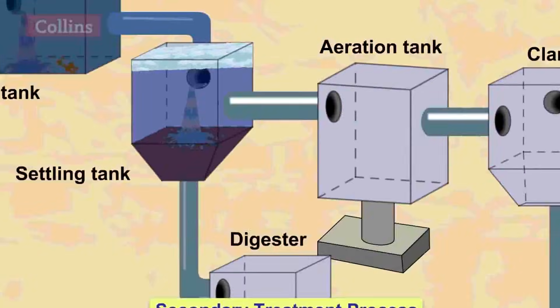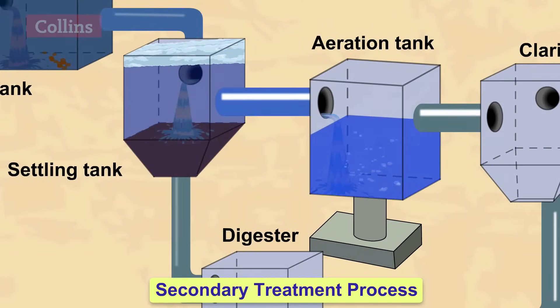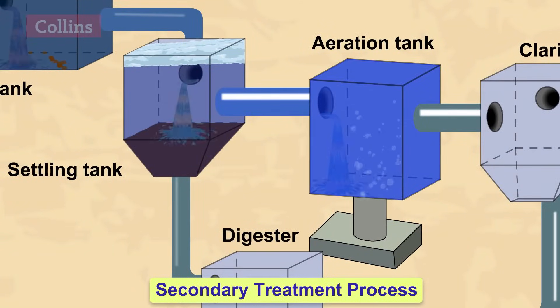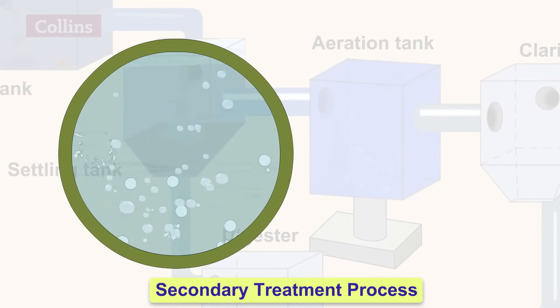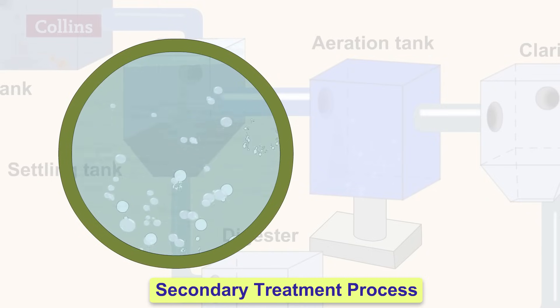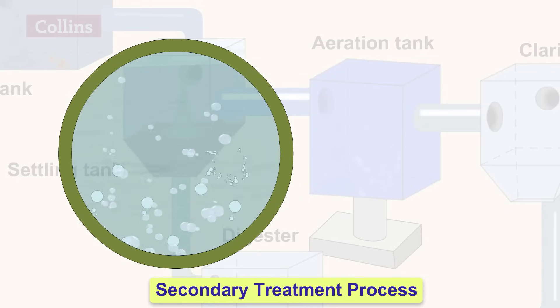In the secondary treatment process, biological or organic wastes are removed. It is a biological process. This is done by transferring the clarified water into an aeration tank where air blowers bubble air, which helps the aerobic bacteria to grow and feed on the organic contaminants such as food waste, feces and other organisms.